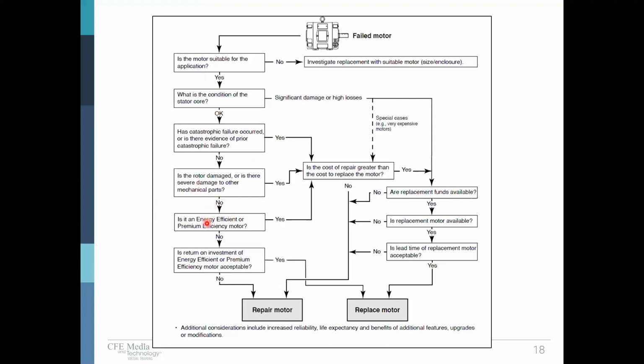So we've gone through those, and let's say these are all no's and okay's. You come down to, is it an energy efficient or a premium efficient motor? If it's not an energy efficient or premium efficient motor, then we want to do an economic evaluation of the repair: on a long-term basis, assess the cost of energy versus the cost of repair over the expected useful production time from that motor. We assess it, and if it's not going to pay off, we're going to repair. If it is going to pay off, we're going to replace the motor.